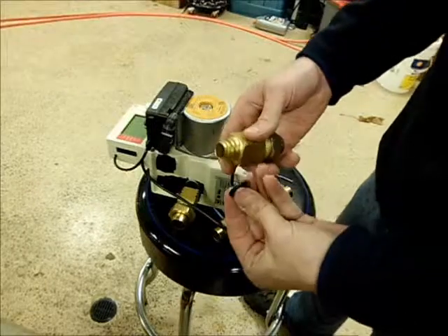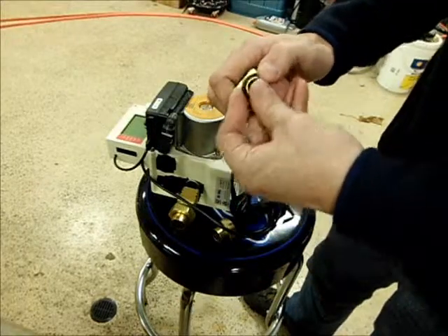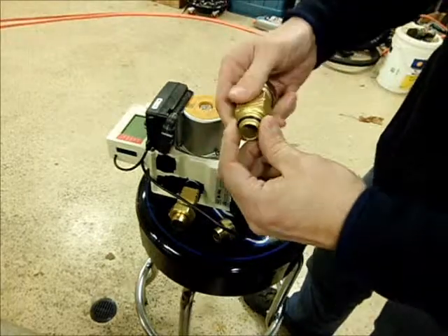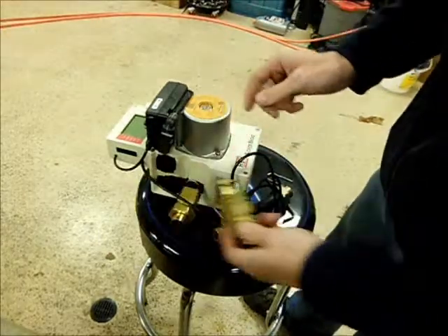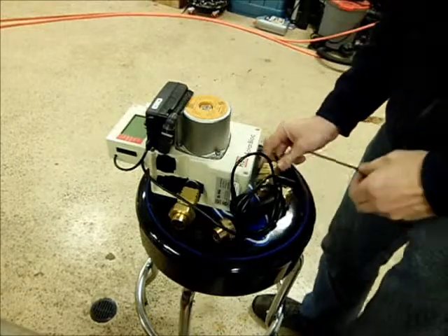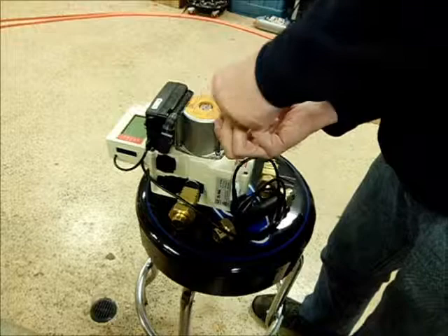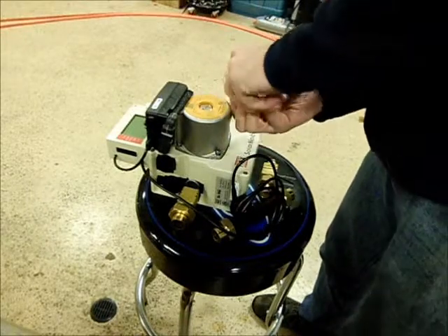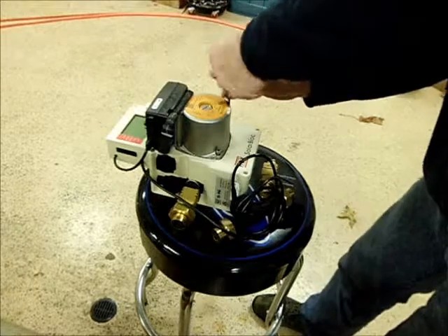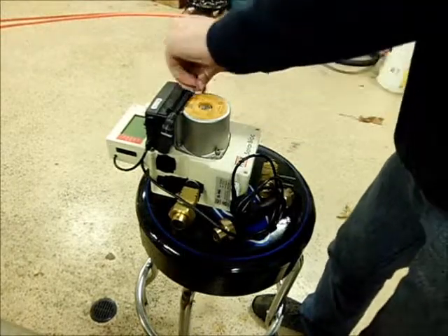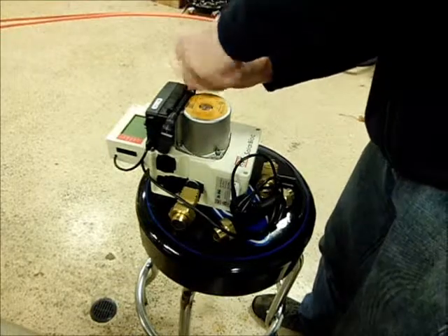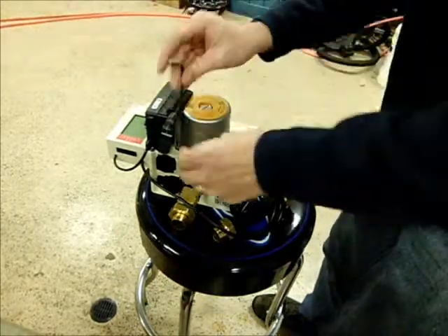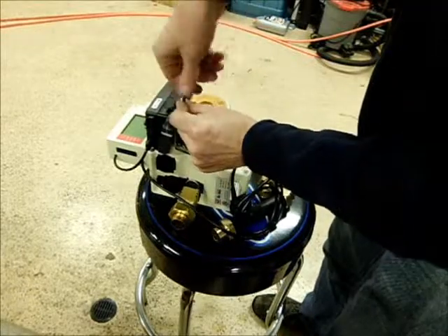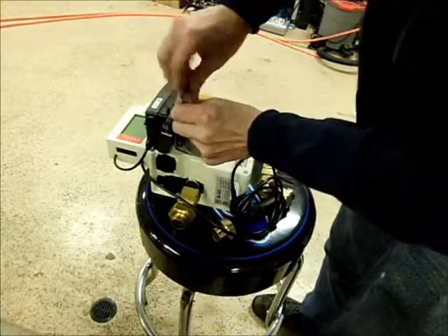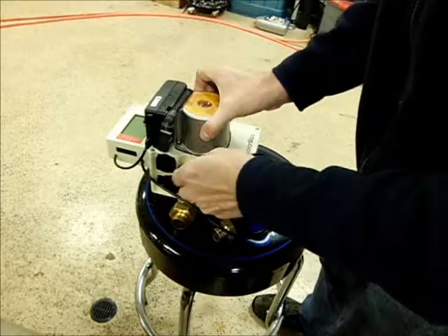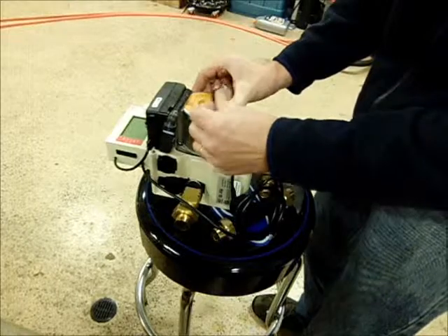Okay, first things first, we take one of the supplied rubber O-rings and basically just work it over the end there. You can use some spit or something to lube that up to push it in the hole once we get the pump off. So to pull the pump off, basically you have to undo all these Allen key bolts here. I've got them mainly undone already. Okay. There's a few cable connections in the pump as well, but there's probably enough slack that we don't have to worry about that. Okay, now we just basically yank up on this guy. Hopefully these are all loose.